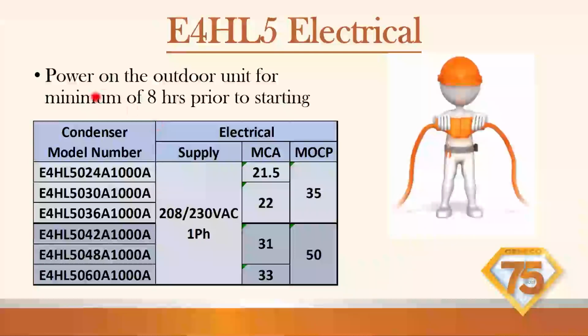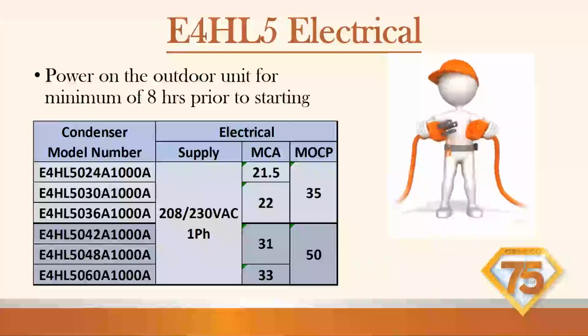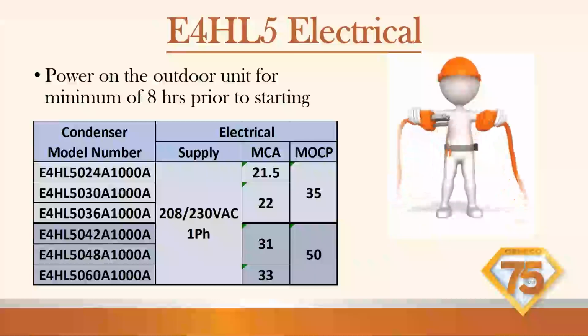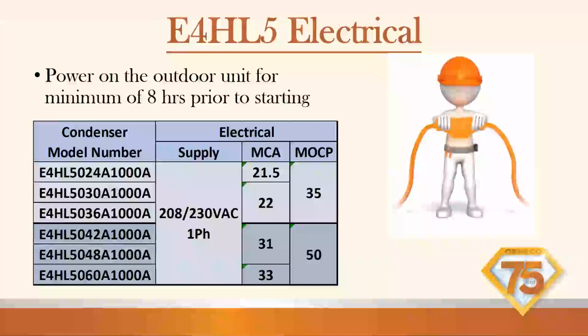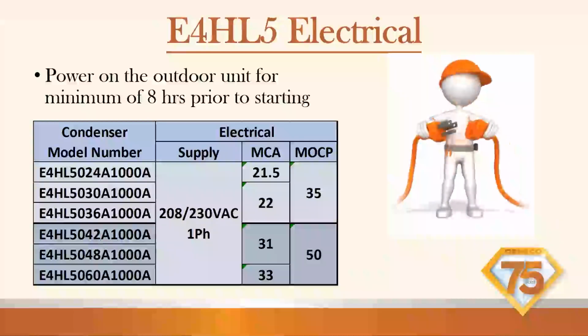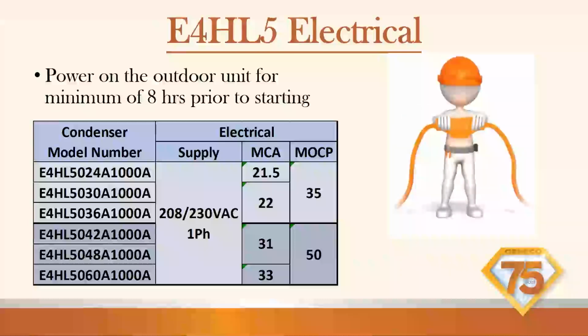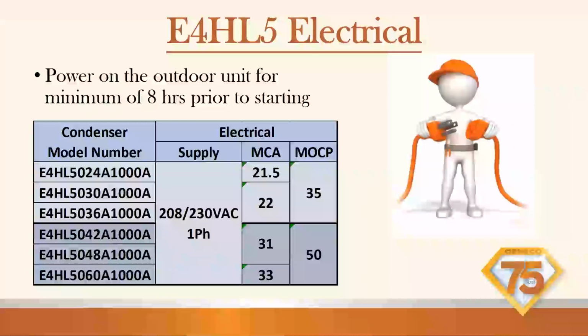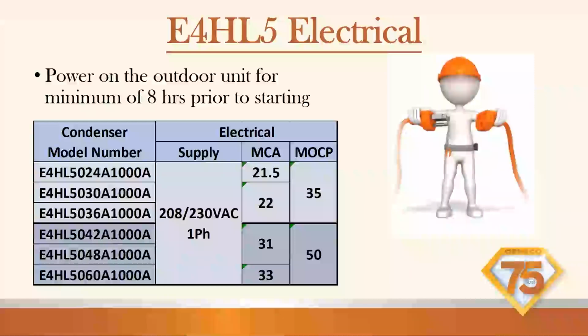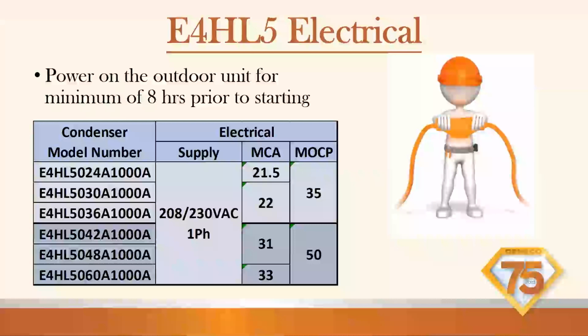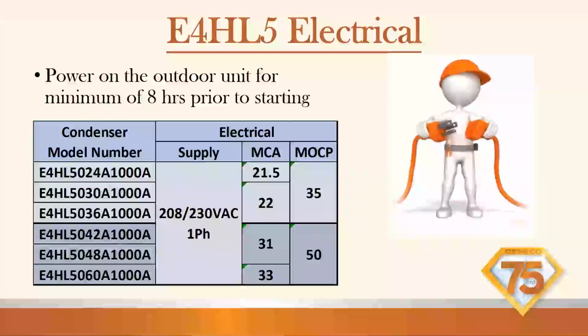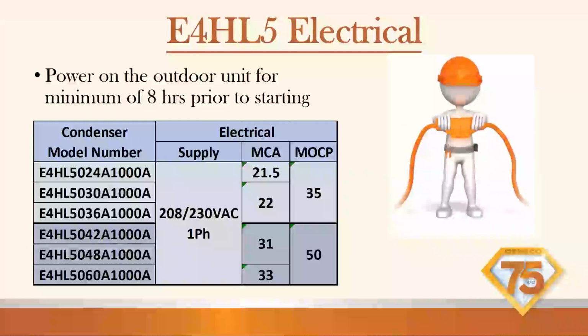This is important. Power onto the outdoor unit for minimum 8 hours prior to starting. Okay, so that is so the heat pump can pre-warm the compressor. It needs to be warm before you start it, or you're going to kill that compressor and lead to premature failure. We deal with that a lot. Compressor possibly fails in 3 months, or it could fail within the first year. I know Mitsubishi's pretty particular on that. If they don't honor any kind of compressor issues because it was not preheated.